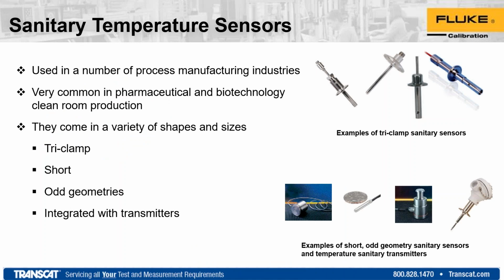Some of the limitations of using a dry well versus a bath are because of sizing. Typically dry wells work best, rule of thumb, for your more traditional sheath type probes that are 1/8, 3/16, 1/4 inch diameter with a variety of 6 inches or longer stem lengths. When you get into some of these different thermocouple designs and transmitters and TriClamps, they're usually very short, so you can't really attain a whole lot of good immersion in a dry well. And a dry well's designed to be used typically fully immersed to get the best results during the calibration process.